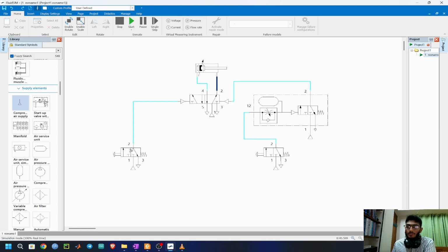See, when I push this button, it immediately extends. When I push this, it closes after a certain amount of time. So if I want to delay more, then I have to restrict more. Okay, let's see. Good. See, now the delay is more. So by restricting more fluid or making the reservoir size bigger, I can set the timer.